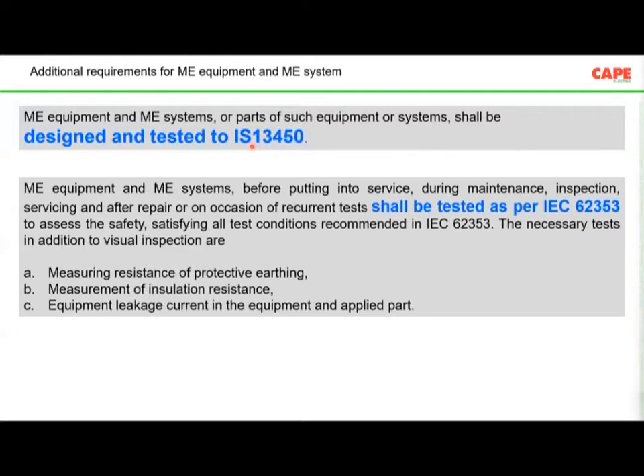Please ensure that all the medical items you are buying and using in your hospital conform to the IS standard. You can also refer to the respective IEC or, sometimes for European products, the EN standard, but check that it is equivalent to the IS standard. Then, in the second para, once you put a new medical equipment system into your electrical installation, or if you do a repair, maintenance or some kind of reconnection, you are also supposed to do testing as per IEC 62353. There is no equivalent Indian standard yet.